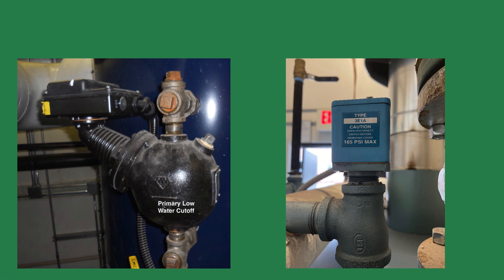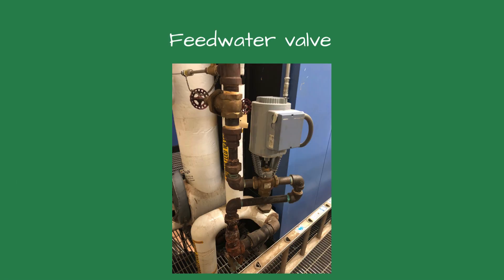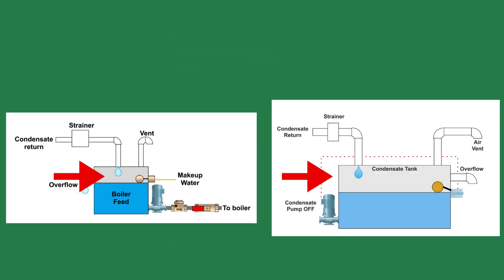The starting and stopping of the pump is controlled by a level control monitored on the boiler. If the plant has two or more boilers, feed water valves or separate pumps are used for each boiler. Both tanks should maintain an air cushion above the water at all times. This allows air to be vented when the steam is on and air to replace the steam when the boiler is off.